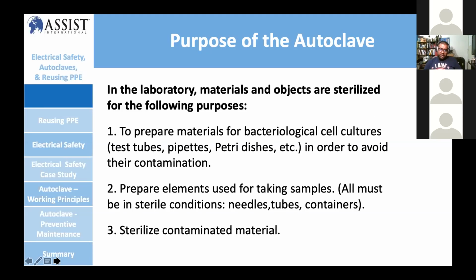So the purpose of the autoclave, everyone knows, it's used in the laboratory to sterilize material and objects. So you're going to clean test tubes, pipettes, all this. Sometimes you're going to use this for your ventilator tubing, the multiple-use tubing. You need to use the autoclave to disinfect the particular tubing. Some might use it for your surgery tools.